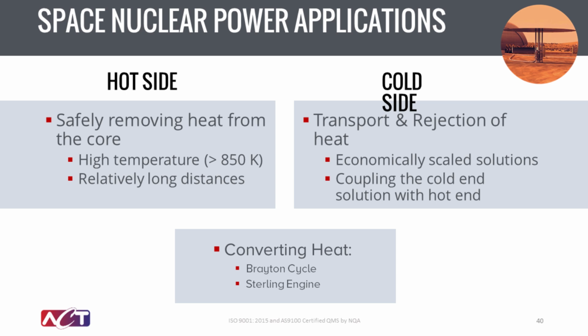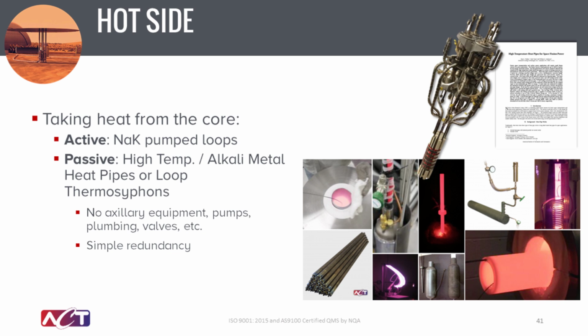On the hot side, the goal is to safely remove heat from the core. These are very high temperatures, sometimes well over 850 degrees Kelvin, and relatively long distance. And the cold side is all about transport and rejection of the heat. It needs to be economically scalable solutions and coupled to the cold end of the converting generator. So on the hot side, there's two primary approaches, similar to what Bryan was discussing. There's both an active and passive. Passive is king in that there's no auxiliary equipment, pumps, plumbing, valving, and then that N+1 or N+2 redundancy. Heat pipes are very simple and have very simple redundancy. And also they look super exciting, like these pictures on the bottom right-hand side when they're operating at these high temperatures.